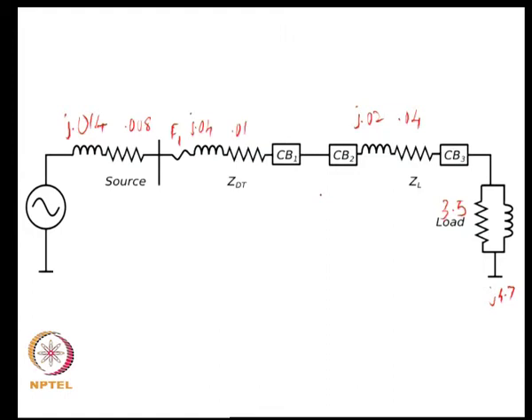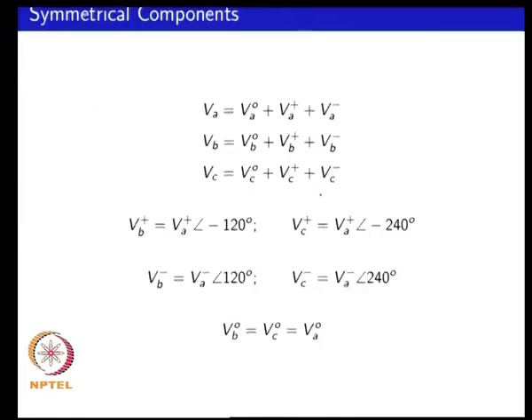What we have looked at so far is the three-phase fault. To look at unbalanced faults — a common fault being a single line-to-ground fault — you will have to look at sequence components. The sequence components on which symmetrical components analysis is based address the unbalanced issue, but it is still a steady-state concept. The quantities you are looking at are phasor RMS quantities rather than peak instantaneous values, which you would need for dynamic analysis.